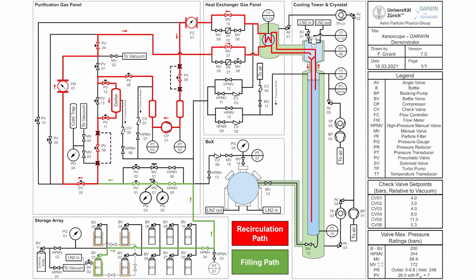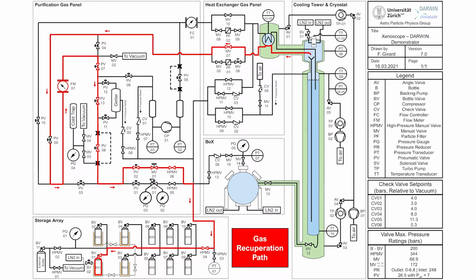The second function of the gas handling system is the filling of xenon gas from the storage system to the cryostat and recuperation back to the bottles. High pressure gas from the storage system is transported to a pressure reducer, allowing us to slowly add xenon to the cryostat where it is liquefied. At the end of normal operations, which can last from several weeks to several months at a time, we can use the gas system to carry the xenon back to the storage vessel in a controlled manner by cryopumping.